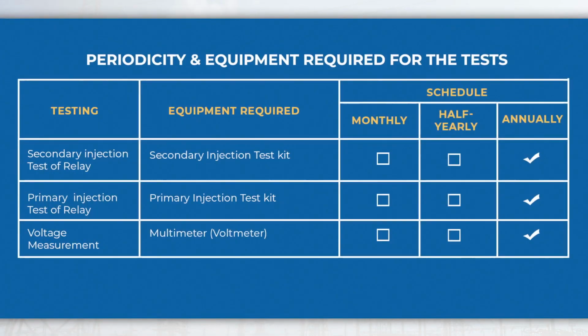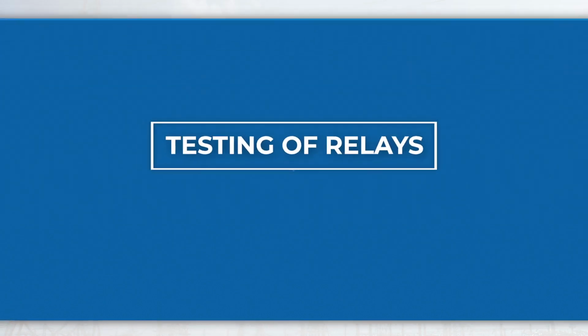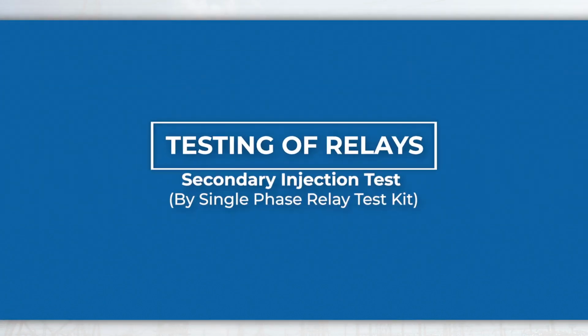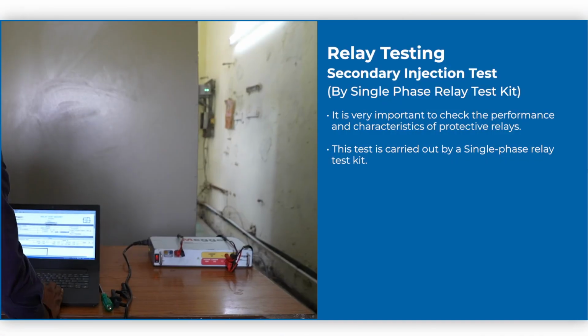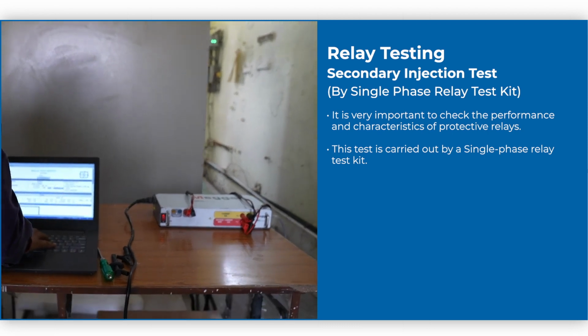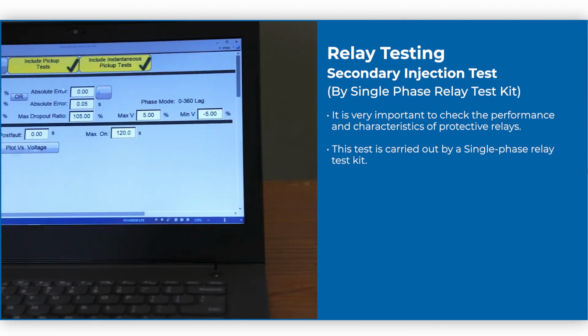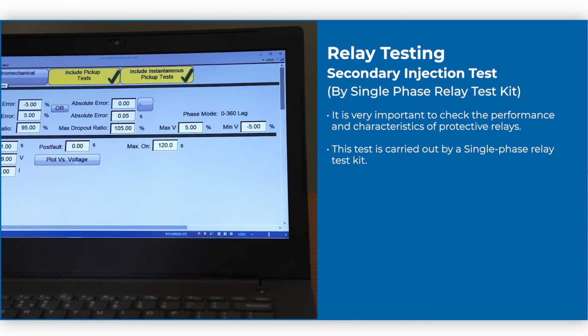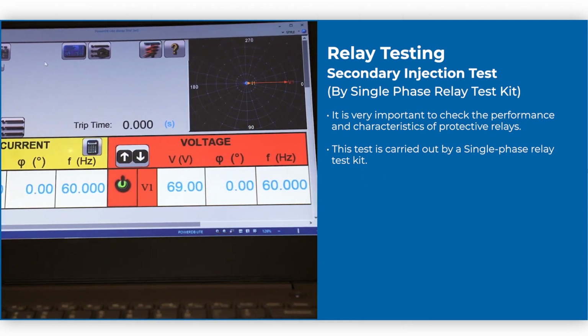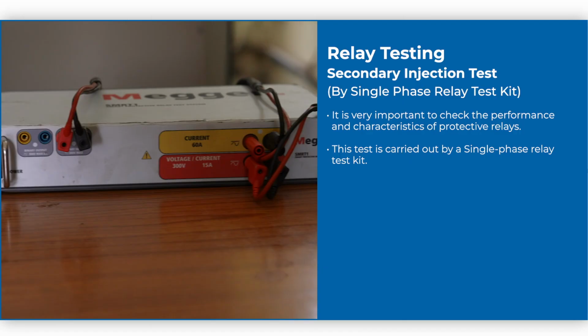Testing. As per the maintenance schedule, these tests shall be carried out at regular intervals mentioned in this table. Testing of relays. Secondary injection test. It is very important to check the performance and characteristics of protective relays. This test is carried out by a single-phase relay test kit.